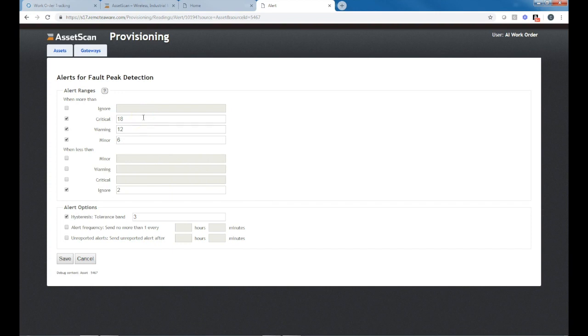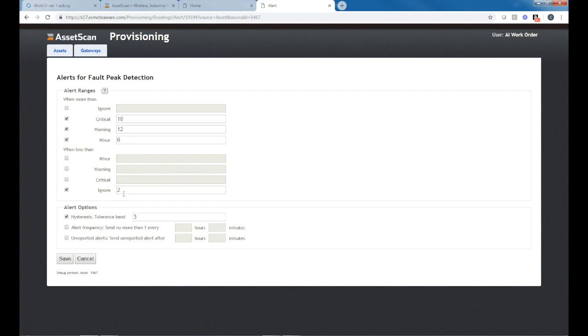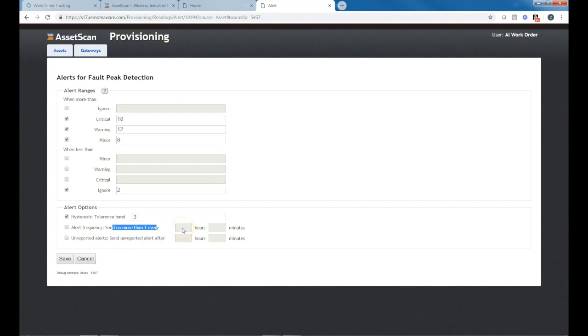What I want to point out here is that the alert management capability. This ignore function means when it's less than two Gs, ignore a reset or a clear of that alarm so we don't generate nuisance alerts. That's important as we generate work orders. We don't want to create additional or nuisance work orders as well. This hysteresis and tolerance band helps us with managing our alerts and therefore additional work orders. And then we have an override based on time so we can set this to say I don't want to get an alert any more than 24 hours or a week on this particular asset.